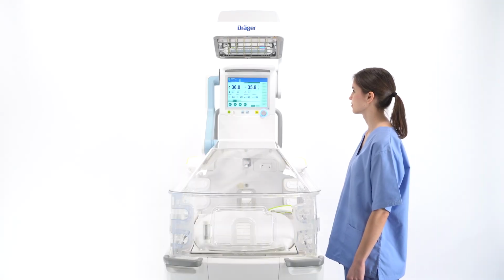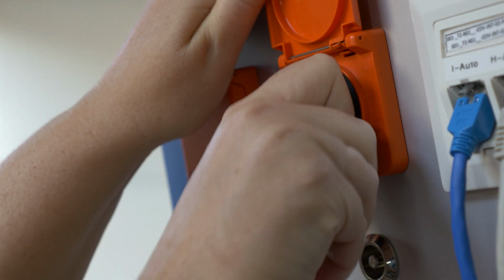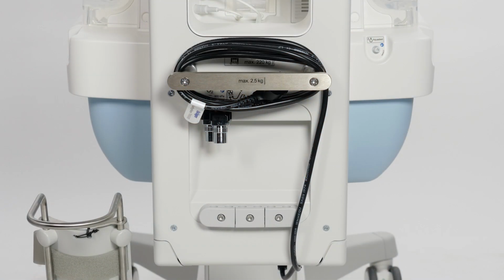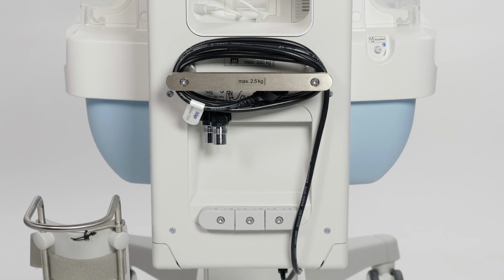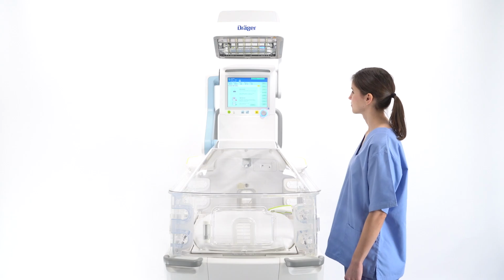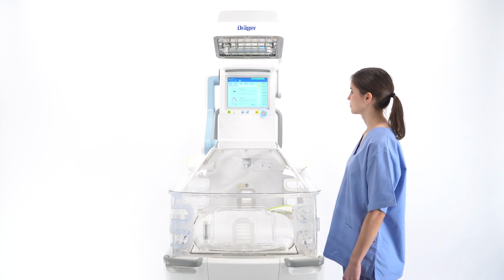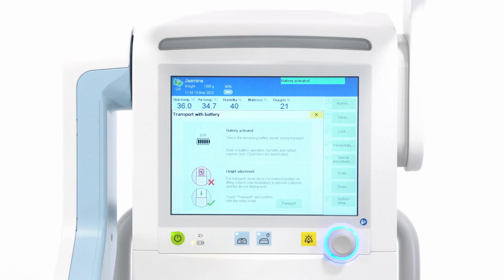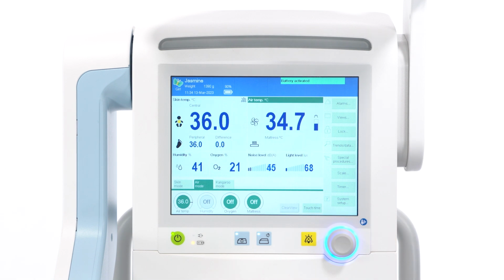Transport can begin after Babyleo has been prepared. To switch to battery operation, simply disconnect the mains power supply. The cable can then be fastened on the back of the device. Monitor all information and the battery charge on the transport with battery screen. Please keep in mind that some functions are deactivated during transport with battery. Touch the transport button and confirm by pressing the rotary knob. The battery activated alarm is now displayed.